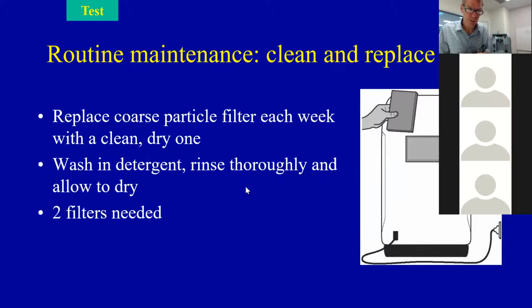I'll just touch on routine maintenance. I talked before about the coarse particle filter. Every week you have to take one out, clean it, wash it in soap and water, and then replace it with a dry one. So for each concentrator you need at least 2 of these, so you can swap them around each week. You wash it in some detergent or an antiseptic, rinse thoroughly, and allow it to dry. Don't put it in front of a heat source to dry, just allow it to dry naturally.